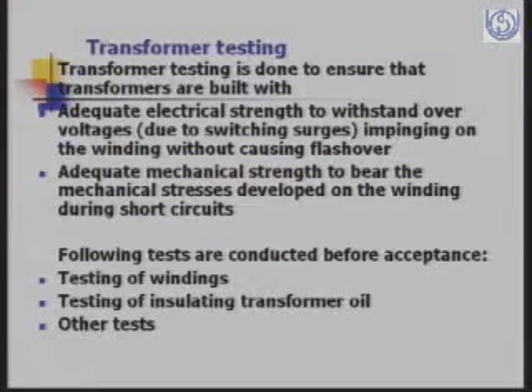Testing of winding of distribution transformers. There are 4 tests which are generally conducted, which are the high voltage test, the induced voltage test, the short circuit test, and the ratio test. The high voltage test. We'll discuss the high voltage test first. This is done to check the dielectric strength of the insulation between the windings operating at different voltage, HV and LV, and between each of these windings, core and the earth part of the transformer. It is also called the major insulation test for the transformers.